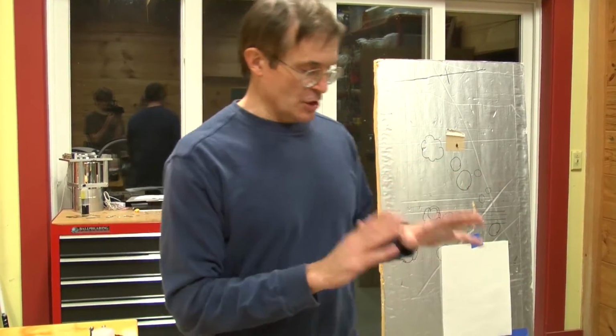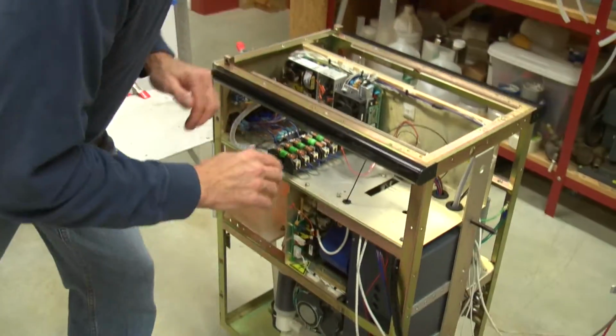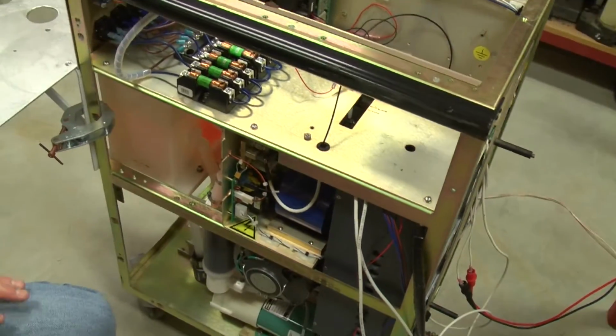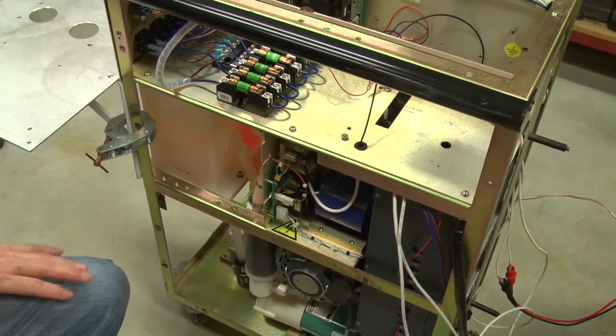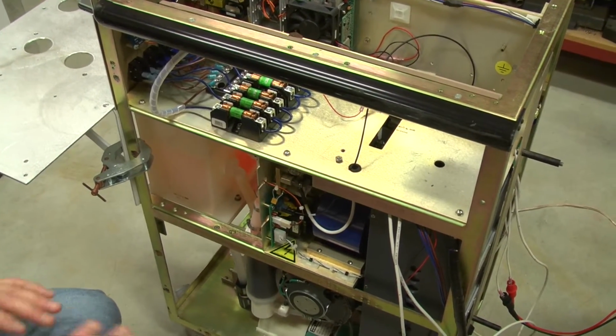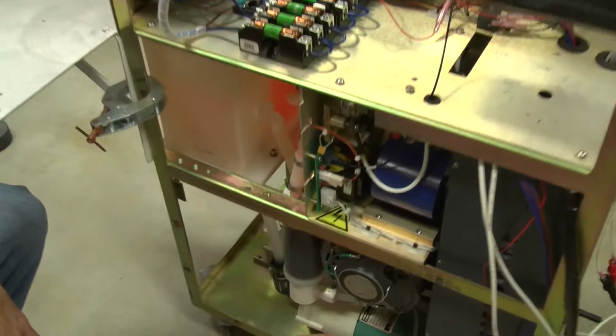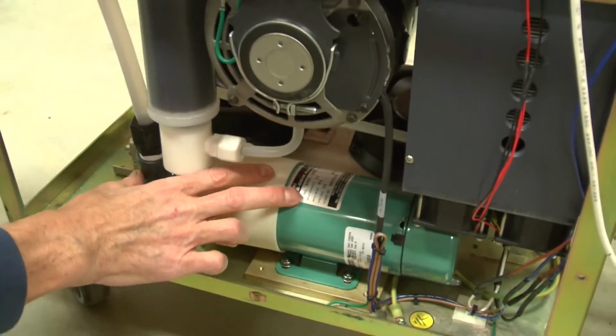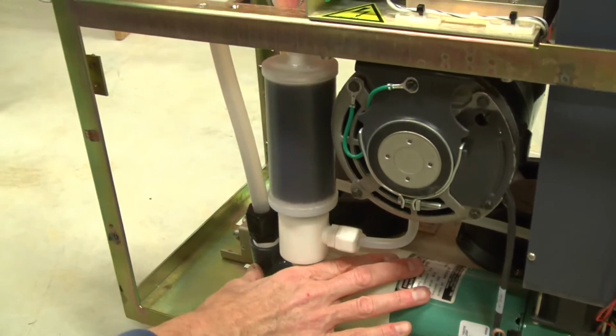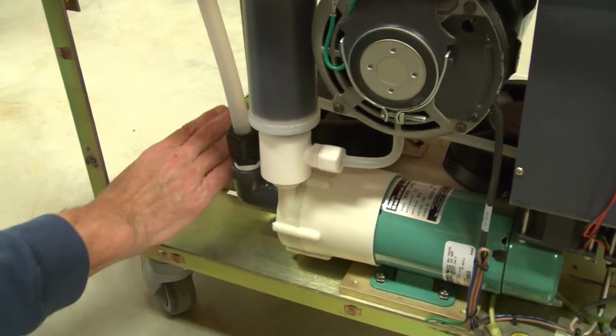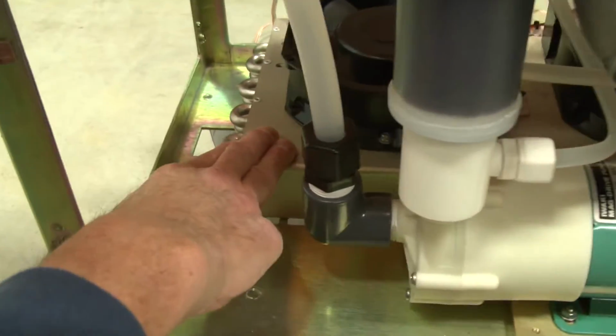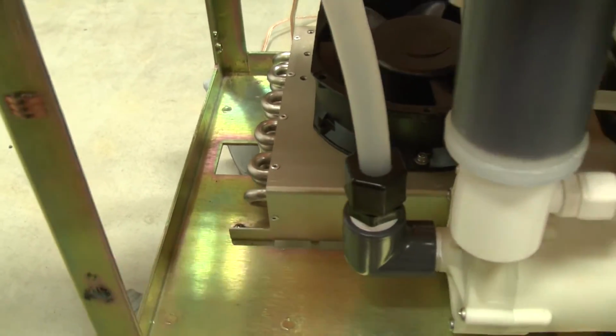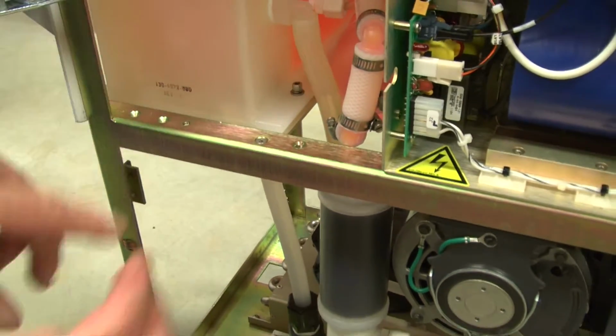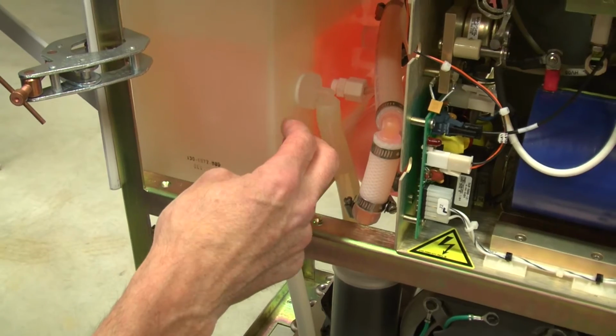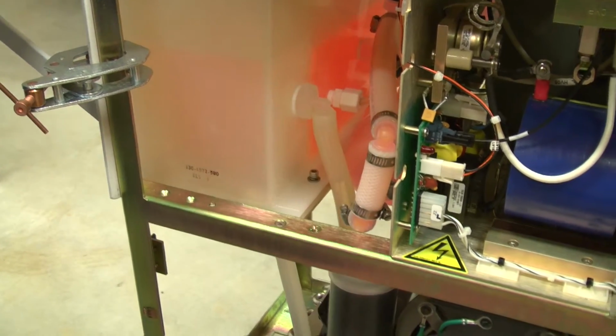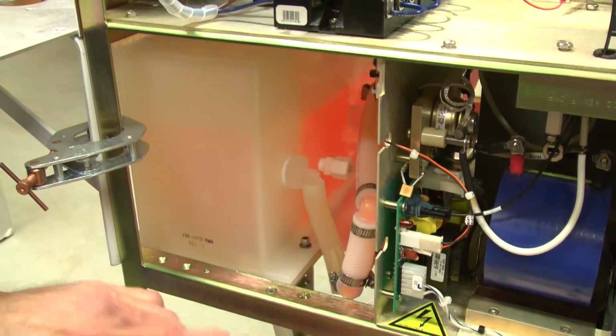Enough theory. The engineering of the laser here. Just to give you an overview of what's going on, so if you ever bought one of these things or thought about building one, you can see how the systems operate. There's effectively two plumbing systems here. One is an Iwaki pump that pumps deionized water, with a deionized filter here, through a radiator located at the bottom of the laser, and then from the radiator up to the head, which I'll show you on the other side, back down to the reservoir, which contains the DI backup supply, and then back through the pump again. So that's the cooling loop that cools the flash lamps.